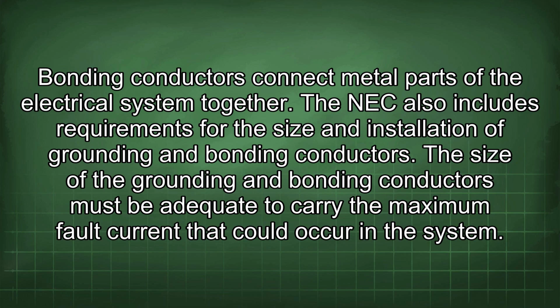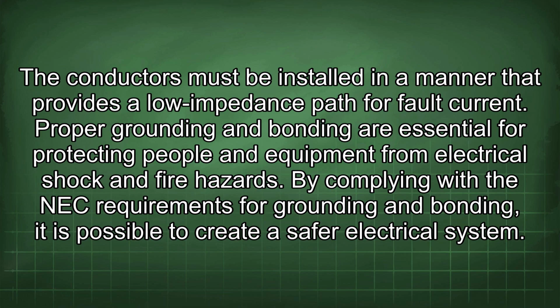The NEC also includes requirements for the size and installation of grounding and bonding conductors. The size of the grounding and bonding conductors must be adequate to carry the maximum fault current that could occur in the system. The conductors must be installed in a manner that provides a low impedance path for fault current. Proper grounding and bonding are essential for protecting people and equipment from electrical shock and fire hazards. By complying with the NEC requirements for grounding and bonding, it is possible to create a safer electrical system.